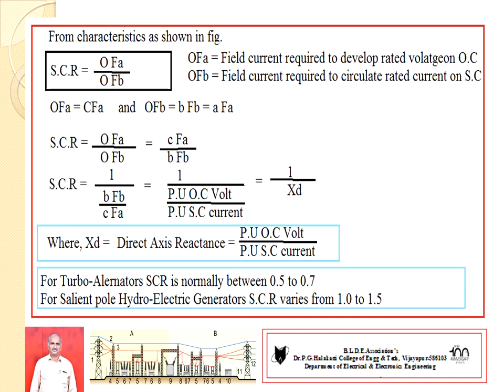For turbo alternators, the SCR value varies from 0.5 to 0.7. For salient pole hydroelectric generators, the SCR value varies from 1 to 1.5.